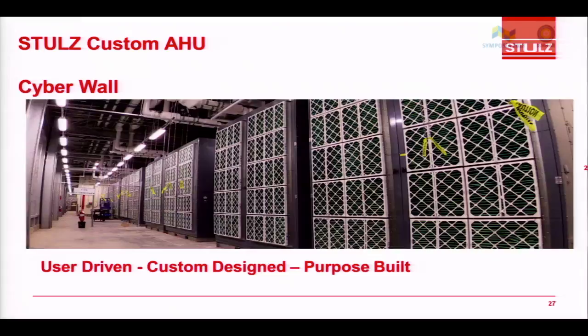And now let's talk about big data warehouses, which Mr. Suresh Balakrishnan said zettabytes. So how to handle zettabytes? Here is how you're going to handle zettabytes. This is called a cold wall. I can't measure the height of the unit, maybe close to 6 or 7 meters. This is called cold wall technology, which has been deployed and is operational. When you talk about big warehouses of data, we don't have an option. We have to use a cold wall of 9 meters high, 6 meters high.